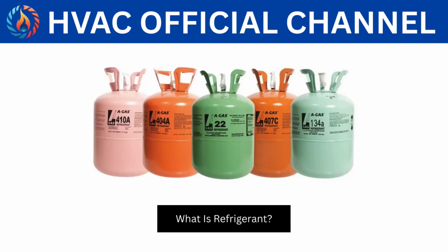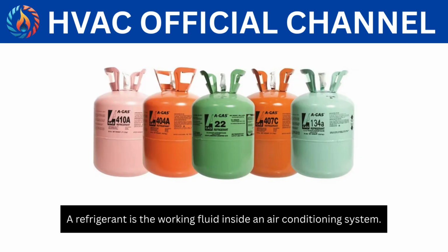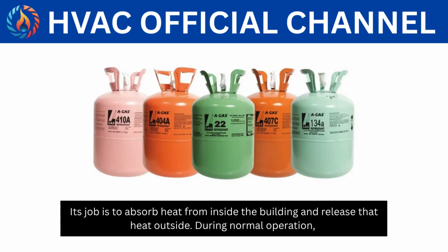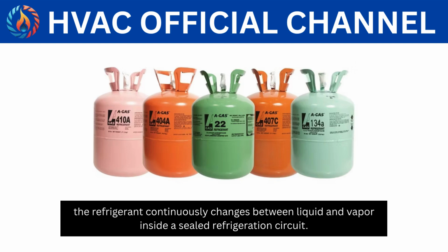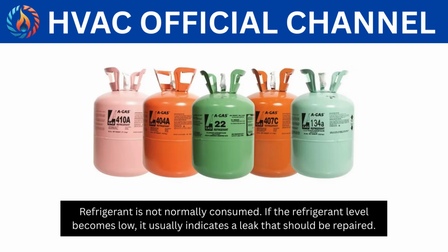What is refrigerant? A refrigerant is the working fluid inside an air conditioning system. Its job is to absorb heat from inside the building and release that heat outside. During normal operation, the refrigerant continuously changes between liquid and vapor inside a sealed refrigeration circuit. Refrigerant is not normally consumed. If the refrigerant level becomes low, it usually indicates a leak that should be repaired.